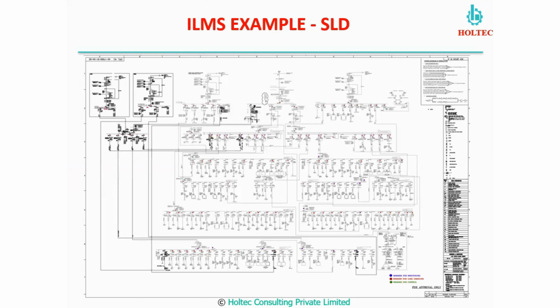So based on the decision taken by the load shedding controller, the reactive and the active power delivered by this generator will be controlled. So in that way, if we take grid power as a reference, with that reference we can do the variation in this generator power. It is possible in reverse also. Normally, when we operate in parallel with grid, what is happening? The grid will be fixed and all variation will be in the grid, and the generator will have fixed load. So if we take over on ILMS, then the grid we can fix, and the variations we can take care of with the various generators available in the system. So in that way also we can achieve it.